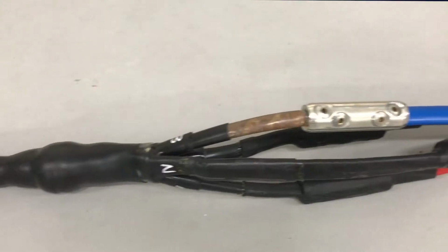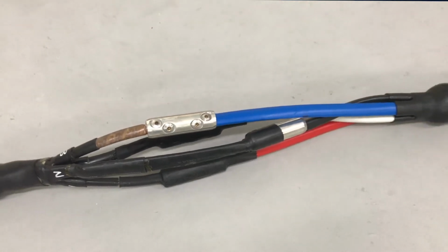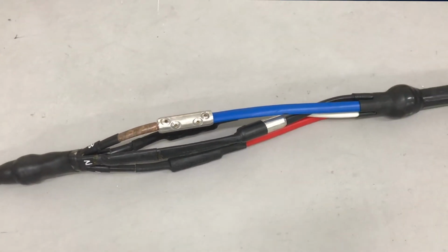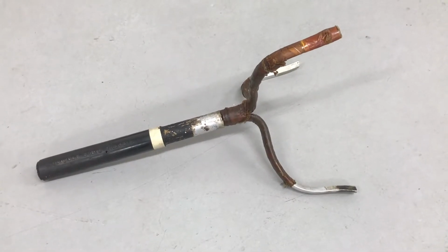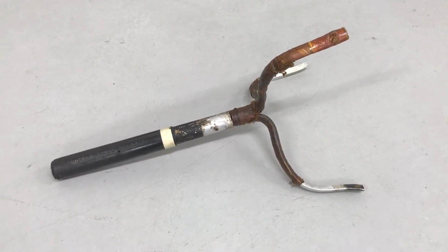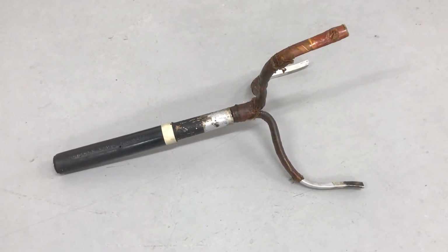In the underground environment, live cable jointing involving straight through or branch joints is not allowed. Any work that disturbs live contact cable, including making or breaking connections, is also banned due to the risk of flashover. Also, making or breaking connections of paper lead cables is not allowed.